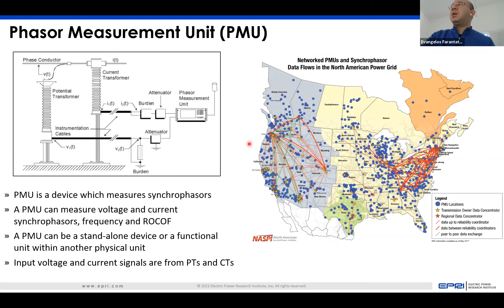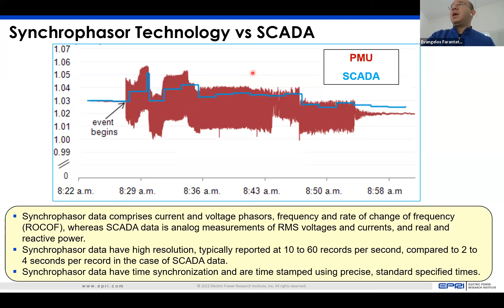In the last few years, we have what we call phasor measurement units, which provide high resolution measurements, and also measurements that are synchronized on a common time reference. These measurement units have a GPS that timestamps and time-aligns these measurements. So this is a comparison between synchrophasors and SCADA - you see the high resolution that allows us to better monitor, but also control the dynamics in the system.